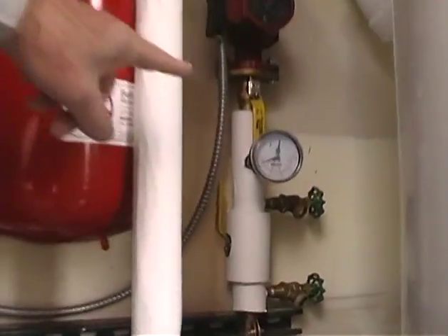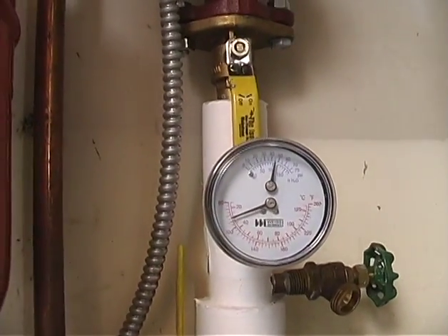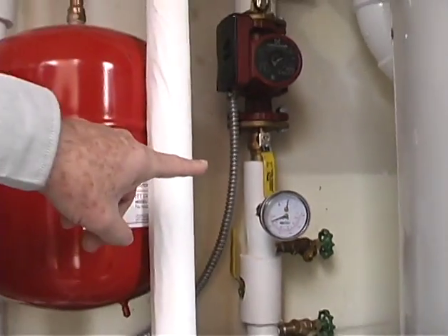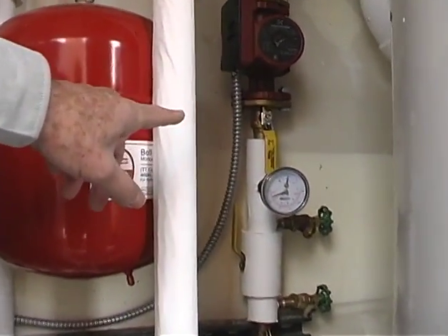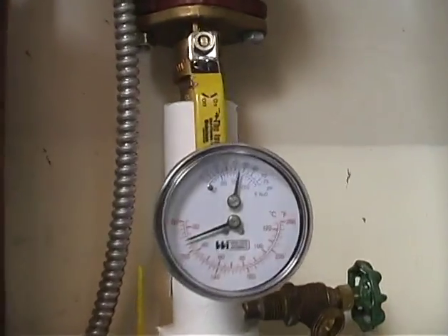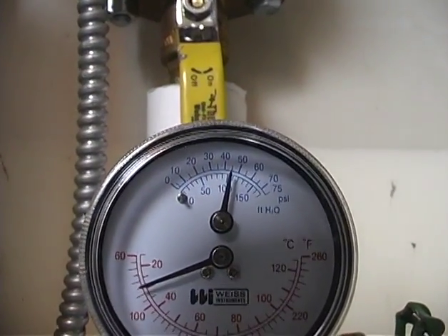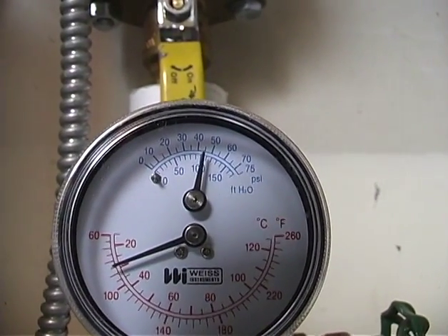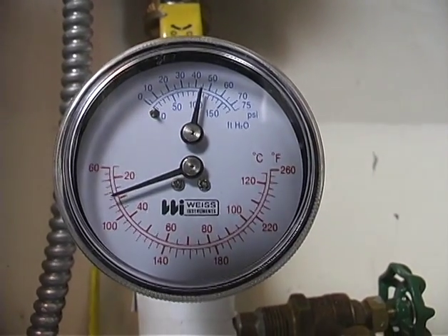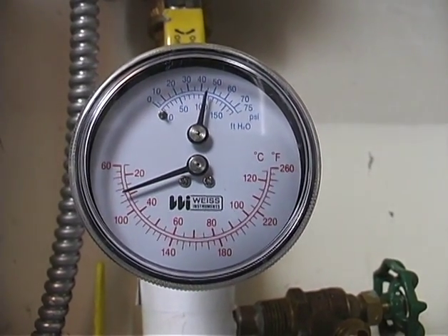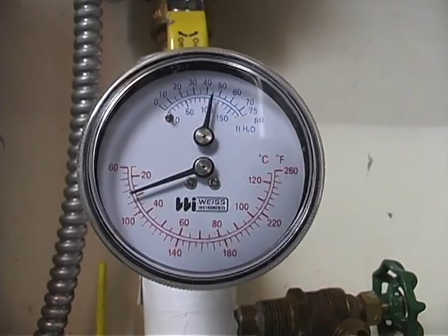The upper blue portion of it shows the PSI, and we set it up to be about 45 PSI. If it drops below 40, there is some kind of loss of liquid, and that's a sign for a problem.